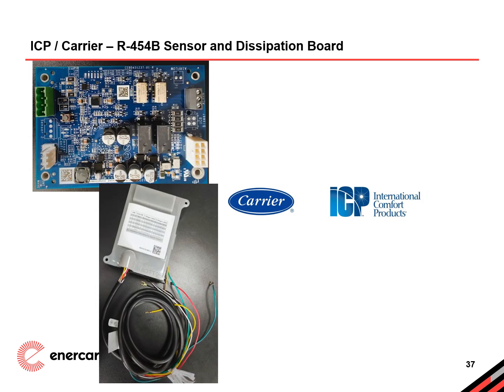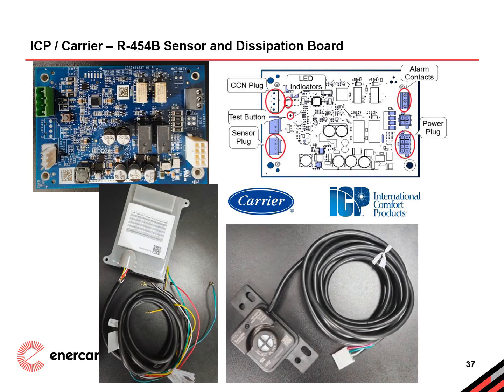As our final example, let's take a closer look at the integration of A2L refrigerant sensors and dissipation boards in ICP and Carrier equipment models. For the foreseeable future, the coils, furnaces, and air handlers will retain the current nomenclature conventions and designs. However, their A2L refrigerant sensor and dissipation board will now be added and wired according to the specific needs of the home comfort system when an AC or heat pump containing R454B is installed. For communicating systems, like those in the Infinity product line, the pictured junction labeled CCN plug will be utilized. Otherwise, the 24-volt wiring harness as pictured on the bottom left will be required.